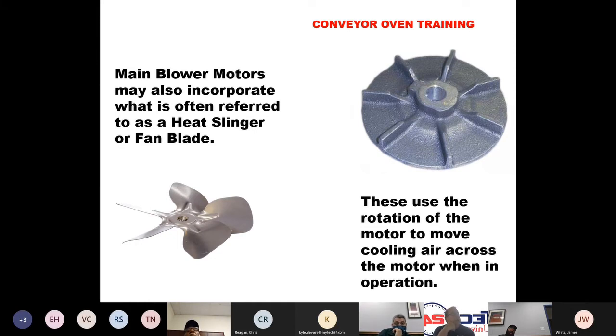The one on the right is called a heat slinger. It's just a little cast aluminum plate. This slides on a motor shaft, and the vanes on that point toward the motor. And as the motor spins, those vanes create an airflow across the motor to keep it cool.